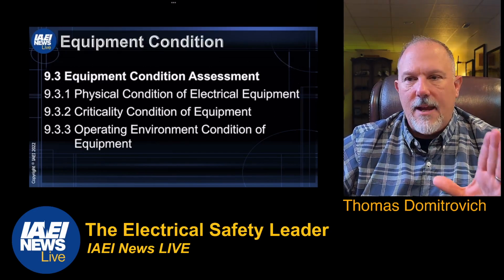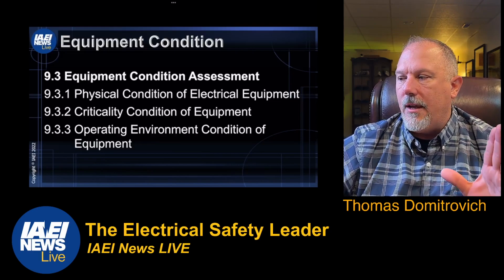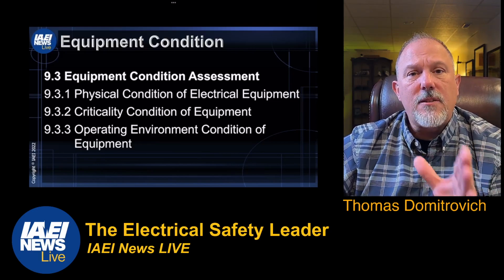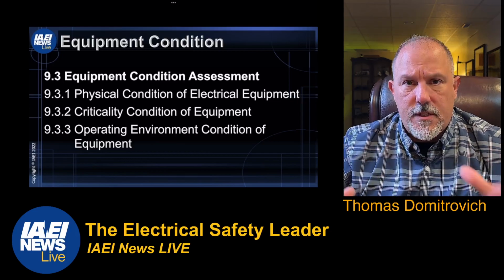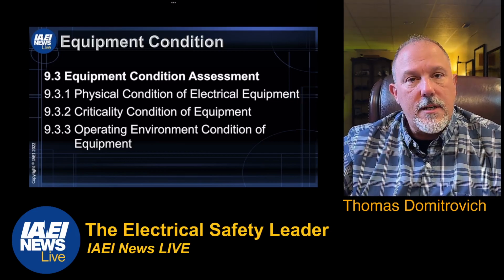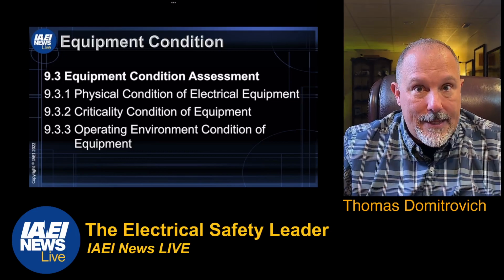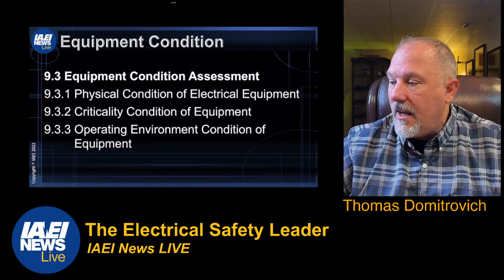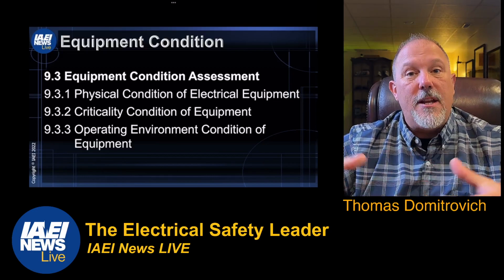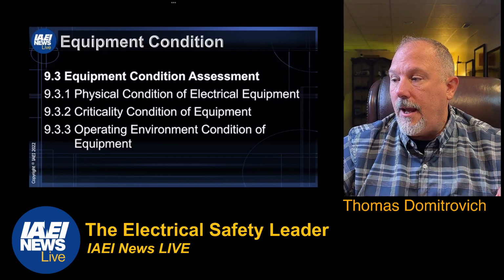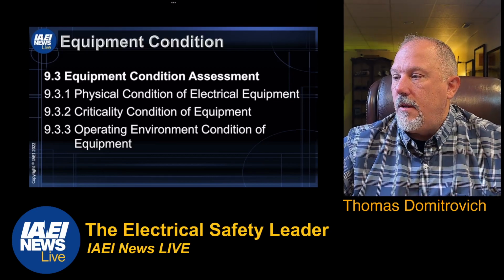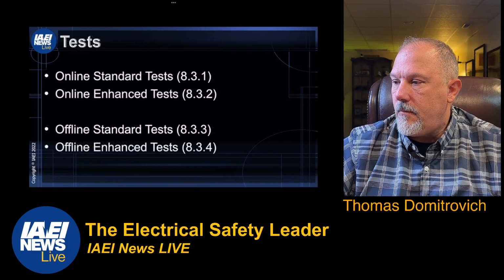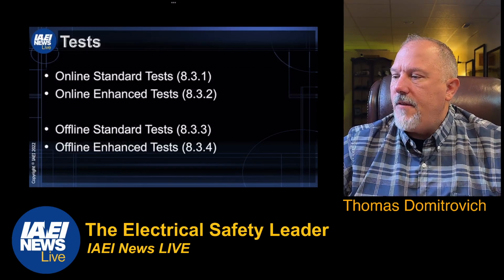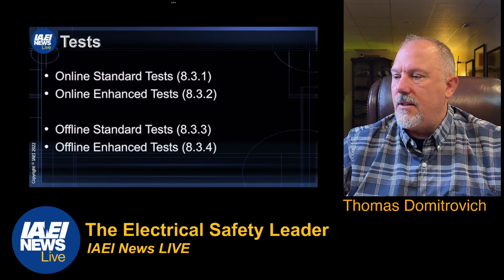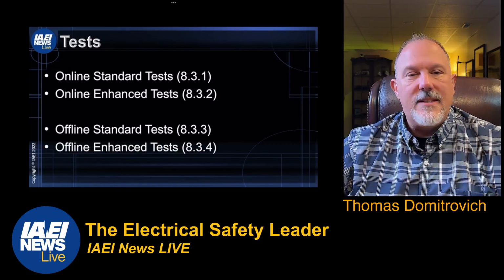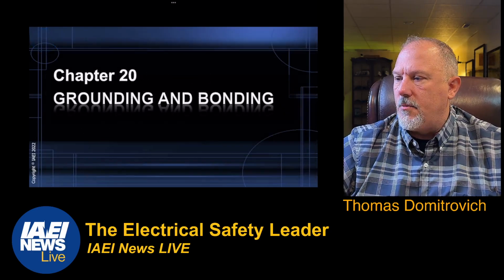Section 9.3.1 through 9.3.3 is your condition assessment. You're going to take a look at the grounding and bonding system in your facility, looking at the physical condition, the criticality of the equipment, and the operating environment of the equipment you're grounding and bonding, and do the assessment to establish the condition and sort of a priority. Then you have your online tests, offline tests, standard and enhanced. We'll talk about those moving forward.